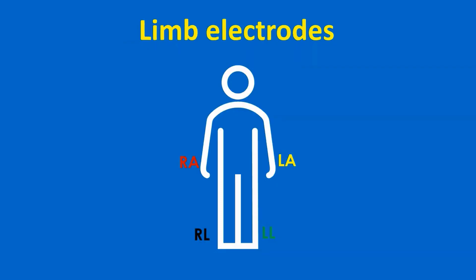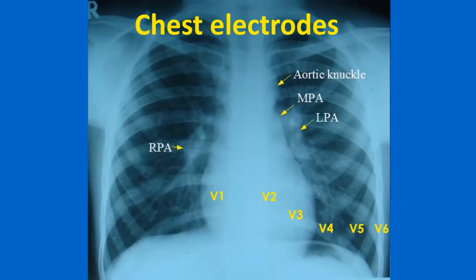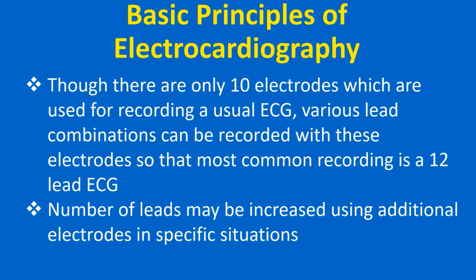ECG uses four limb electrodes on each of the four limbs, of which the electrode on the right leg is considered electrically neutral while the other three are active electrodes. In addition, six electrodes are placed on specifically designated parts of the chest to get chest lead recordings. Though there are only 10 electrodes used for recording a usual ECG, various electrode combinations can be recorded so that the most common recording is a 12-lead ECG. The number of leads may be increased using additional electrodes in specific situations.